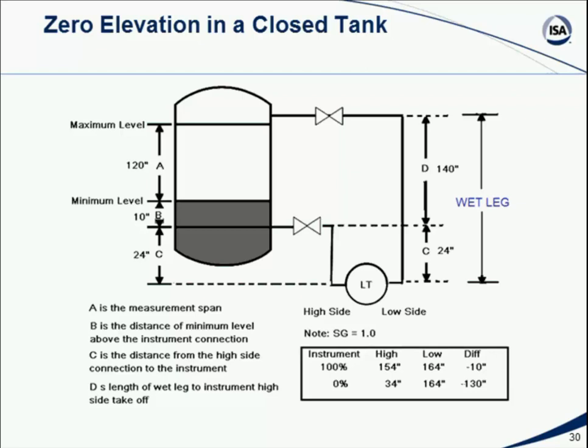So instead what we'll do is intentionally fill that high leg with fluid and just treat it as our high leg with our high pressure, and we'll flip our transmitter around and look at the pressure difference between the high column of fluid, which is this filled leg, and the actual fluid level in the tank itself. So if we have a closed tank where we have the possibility of the dry leg becoming wet, then we just fix the problem by making it wet. And so there's fluid in both legs, but the fluid column in the upper leg is stationary, and it's always at the maximum value, and the fluid in the tank goes up and down. As it goes down, the difference becomes greater. As the fluid level in the tank goes up, it becomes less. So it's inverse acting. But again, we can correct for all this, and we can calibrate our instruments appropriately and still get an accurate measurement of what's in the tank.